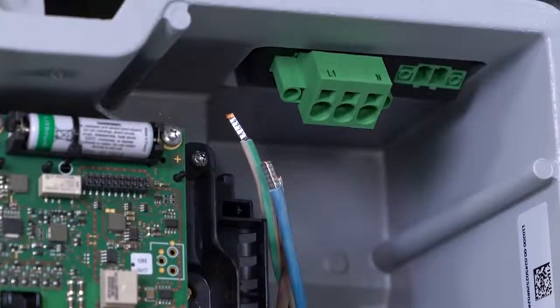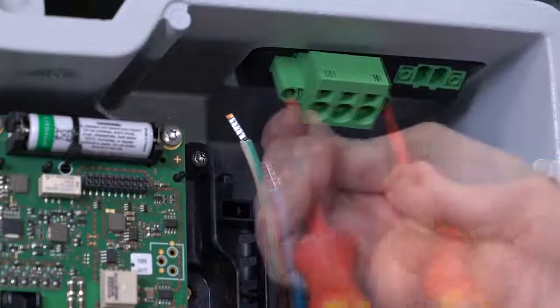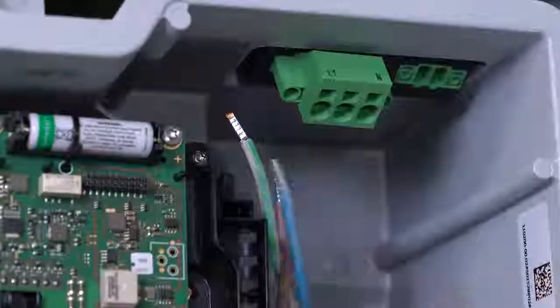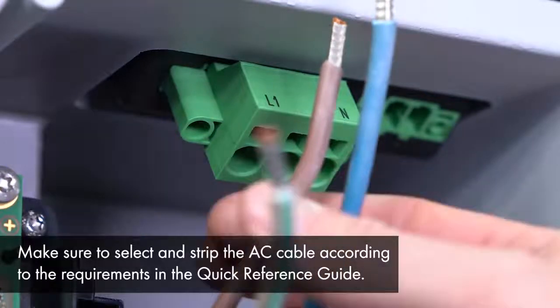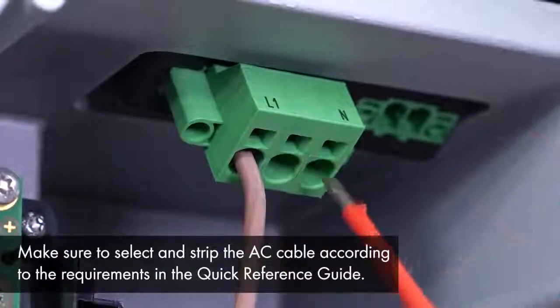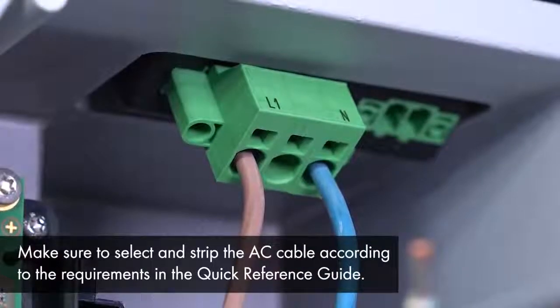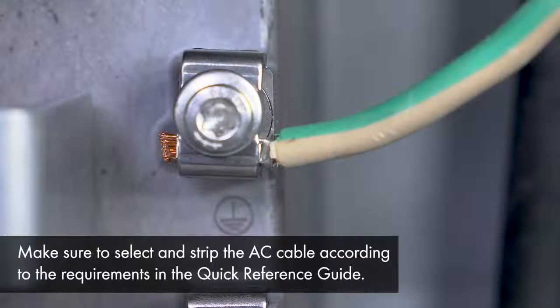It should then be tightened with a 3.5 mm flathead screwdriver. Now, connect the two AC cables, phase and neutral, to the AC plug. As you can see, the flathead screwdriver comes in very handy for this also. The grounding cable must be connected separately to an equipment grounding terminal between the washer and the clamping bracket. Then, tighten the screw with a torque screwdriver TX25.